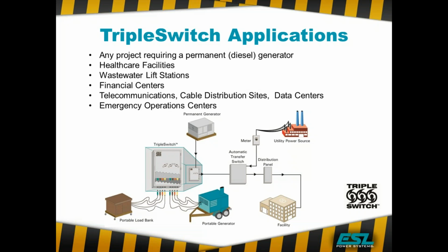So any place that you have a permanent generator, a triple switch should be considered to provide the most complete solution to making sure you can properly maintain that generator. And as you're talking to your clients, you have to make them realize they're investing a lot of money in this permanent backup generator system with the generator, the ATS, the controls, the fuel tank, all of that. They should have a way to properly maintain it and back it up. And this only adds a very small percentage to the cost of not only the emergency power system, but also to the total facility. So it's not typically putting a lot of stress on any budget to provide them with some reliability in the future.